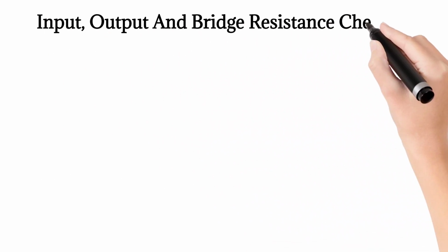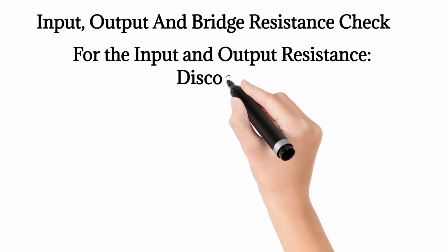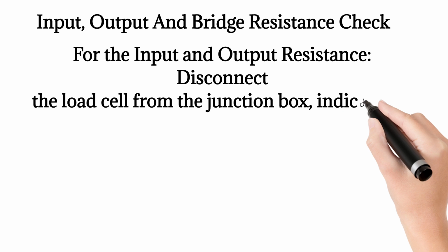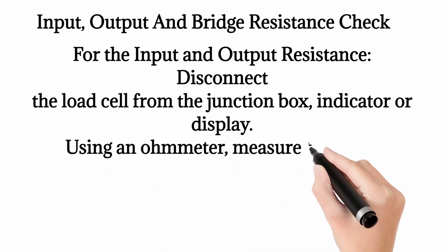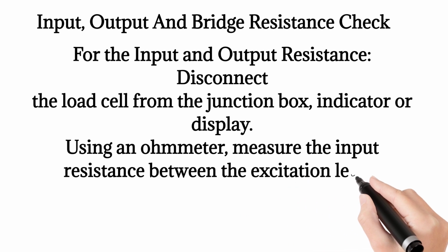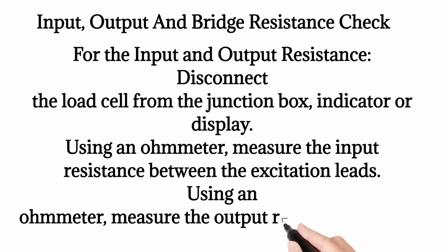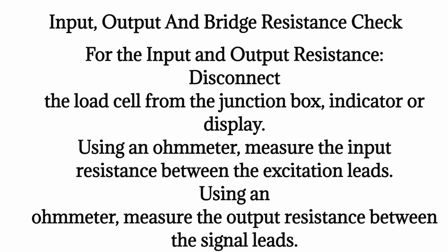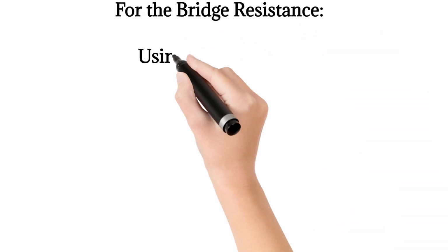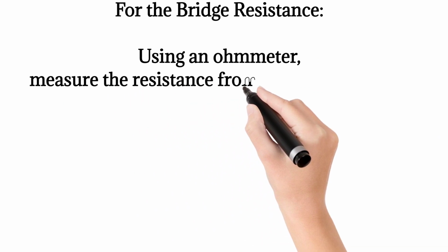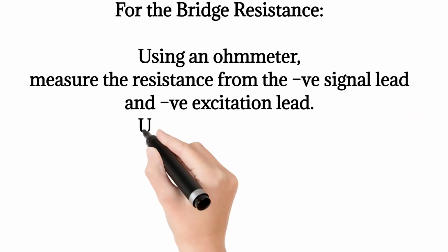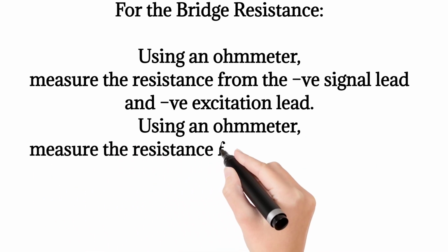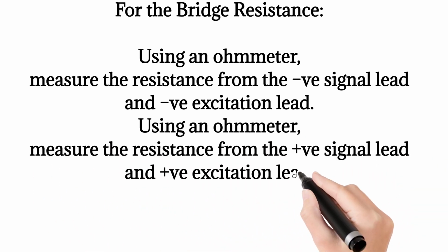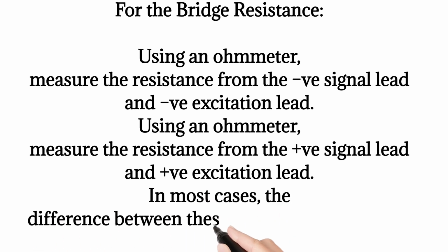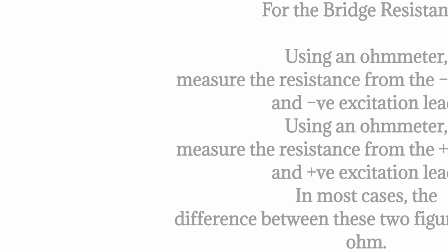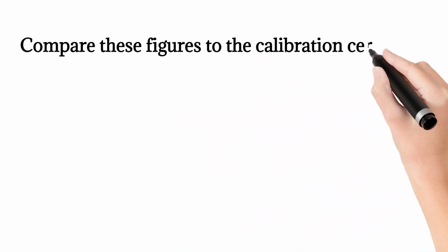Input, output and bridge resistance check. For the input and output resistance, disconnect the load cell from the junction box, indicator or display. Using an ohm meter, measure the input resistance between the excitation leads. Using an ohm meter, measure the output resistance between the signal leads. For the bridge resistance, using an ohm meter, measure the resistance from the minus V signal lead and minus V excitation lead. Using an ohm meter, measure the resistance from the plus V signal lead and plus V excitation lead. In most cases, the difference between these two figures must be less than or equal to 1 ohm. Compare these figures to the calibration certificate or datasheet.